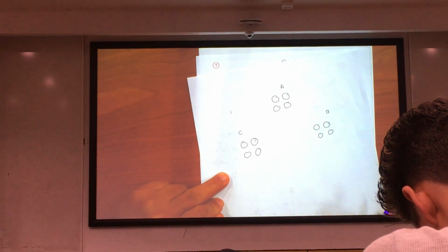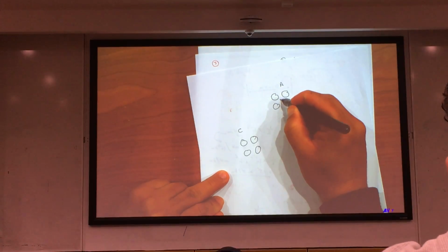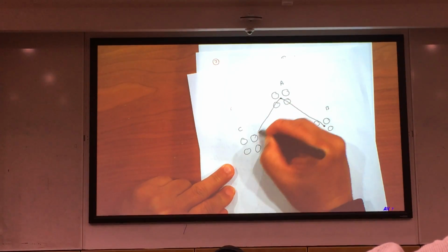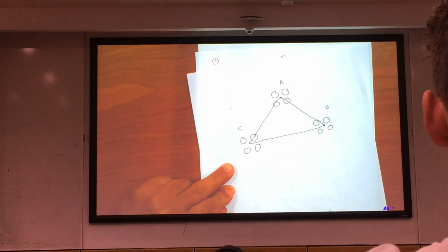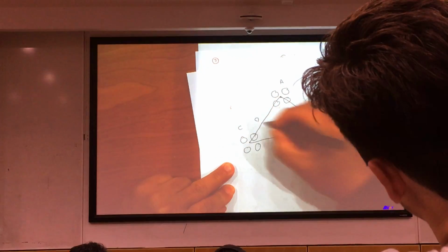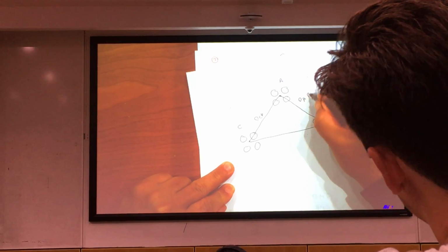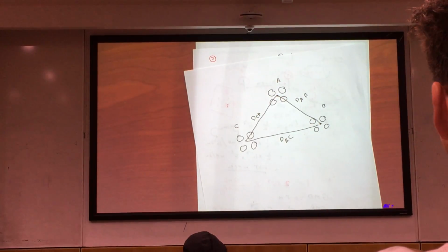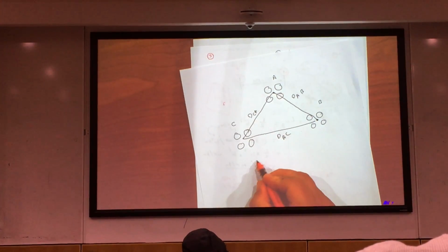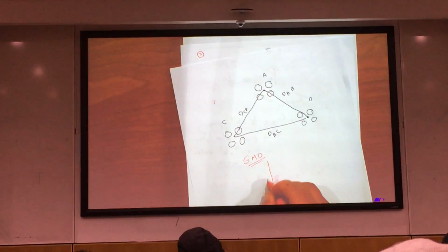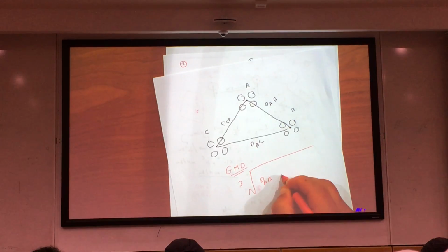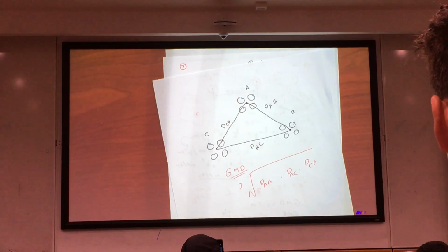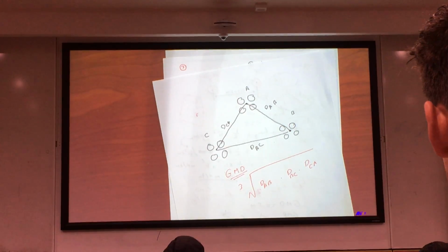Your distances will be measured from the center of the four conductors, this center to this center, and this center to this center. So that's DCA, DAB, and DBC. So you can always use this formula, the cubic root of DAB, DBC, and DCA, to calculate the geometrical mean distance, measured from the centers of the conductors, because we have four conductors in each.